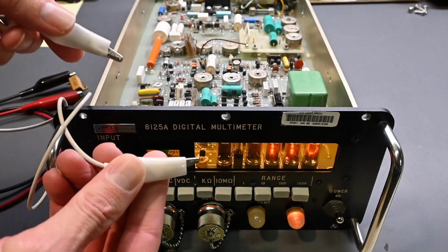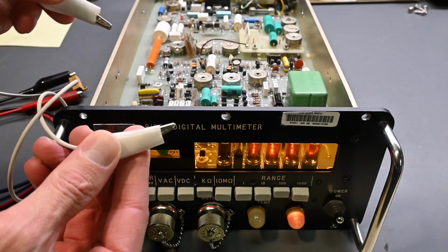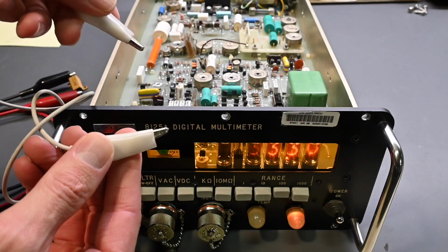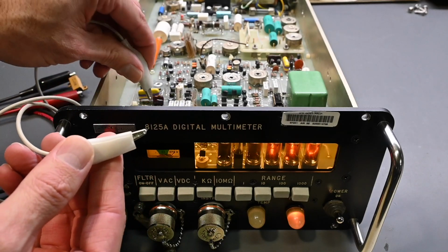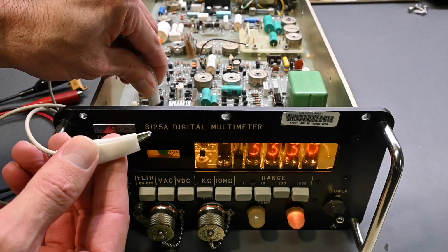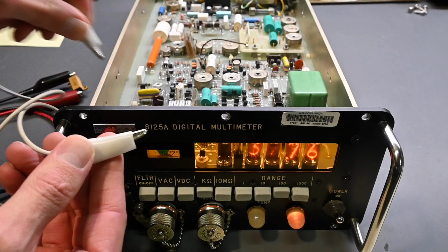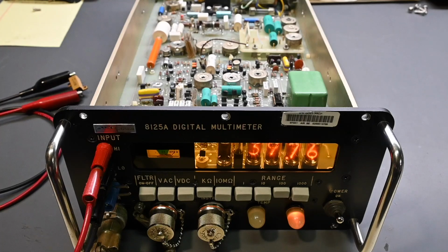And if I take this test lead like before, I won't touch anything on this side. And if I take this other test lead end and touch it to this test link jumper number 1 right here, so there it goes. So now it's locked in, very stable reading, so 39.75 K ohms. Now the instrument has not been calibrated, but that's reading very, very close. And the display flicker that you see right now on the camera is not apparent to my eye. It's very stable.